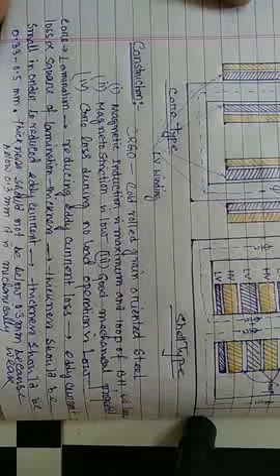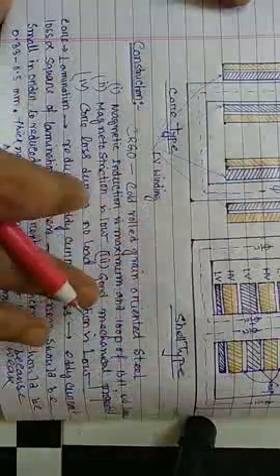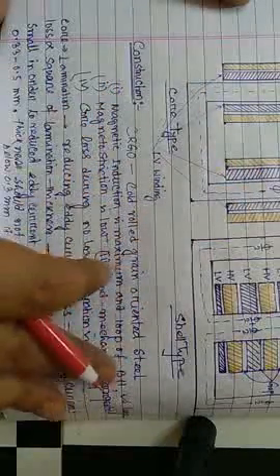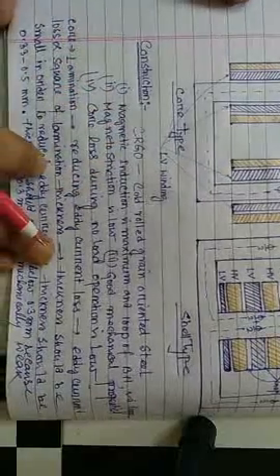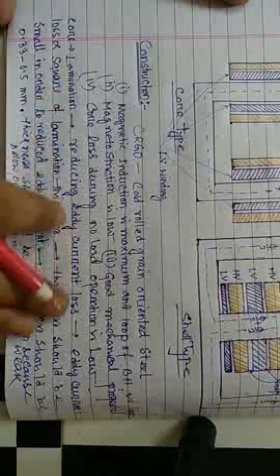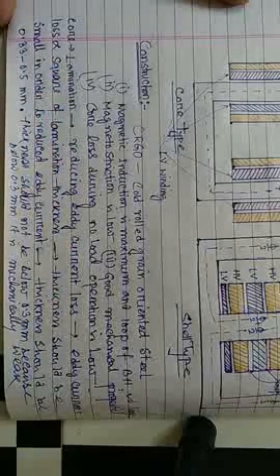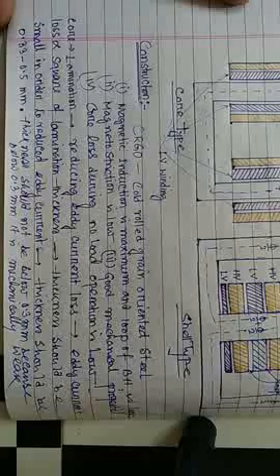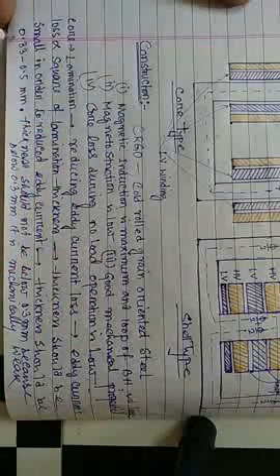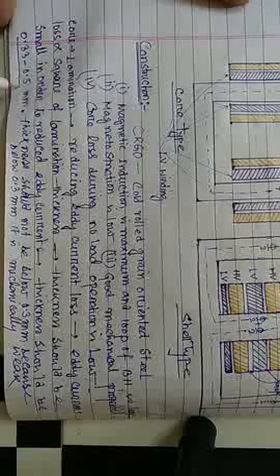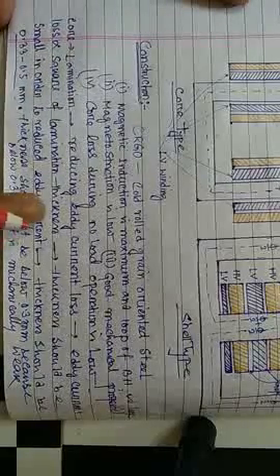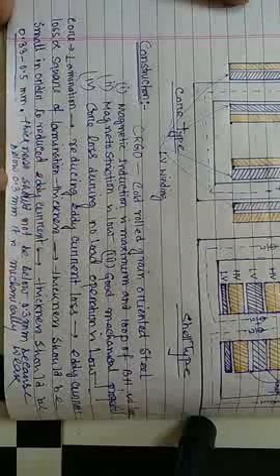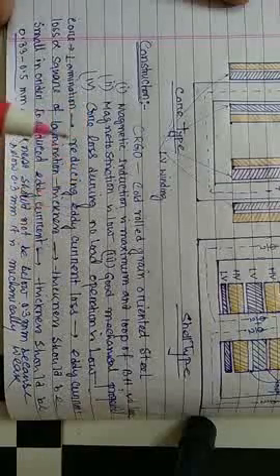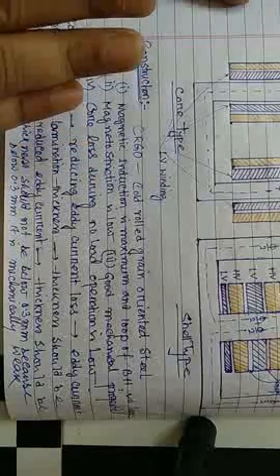So, very simply, the core is made of CRGO. Why CRGO is used, we have already discussed. And the core is laminated to reduce the eddy current loss. Eddy current loss is proportional to the square of the lamination thickness. The lamination thickness should be 0.33 to 0.5 millimeter. The thickness should not be below 0.3 millimeter, because below that it is mechanically weak.